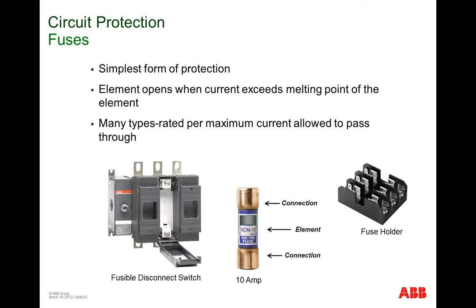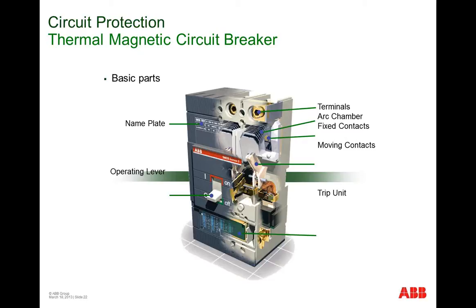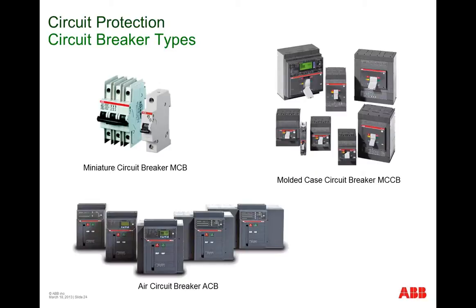There are 2 types of devices that protect circuitry. Fuses are the simplest form, and they are lower in cost, but they are consumable. So if you blow a fuse, you do need to replace it. The other form of circuit protection is called a circuit breaker. It is resettable, so it is not consumed like a fuse, but it does cost more because it's a more complex machine. These provide thermomagnetic protection, meaning that they sense both excessive heat being generated downstream, and they also recognize excessive current that creates a magnetic surge. In both cases, the circuit breaker will trip to protect the equipment downstream.